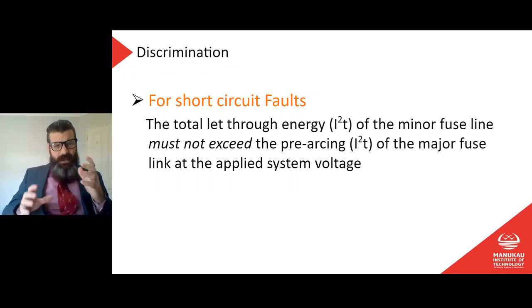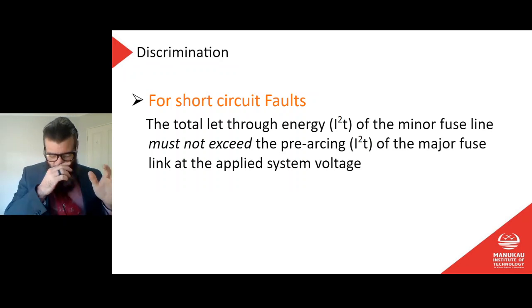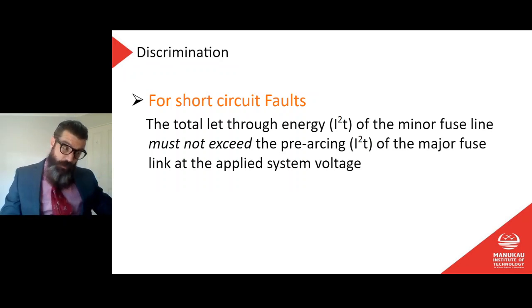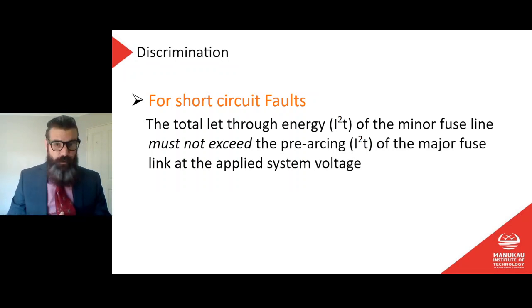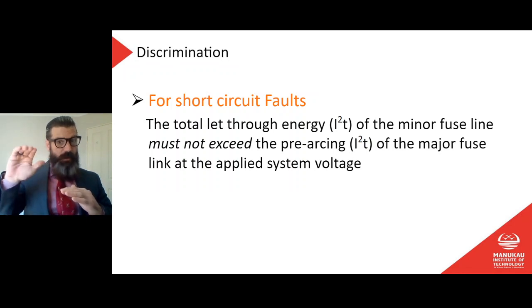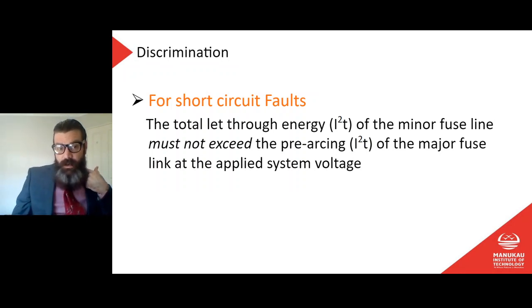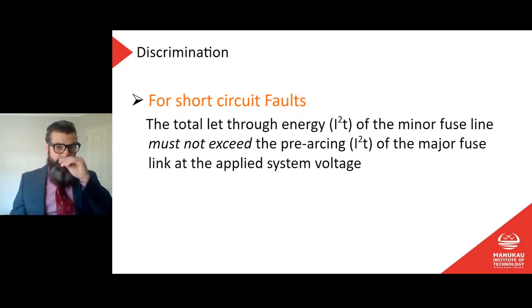So what we're saying here is that we talked about discrimination, and we said that the smallest device, or the closest to the fault, so furthest down the chain, is the one that must trip first. So the pre-arcing time of a fuse is the amount of time that after the fuse decides it wants to trip, before it actually starts to break down. So our total let through energy on the minor fuse link, that's the closest to the fault or smaller fuse, must not exceed the pre-arcing energy of the major fuse link.